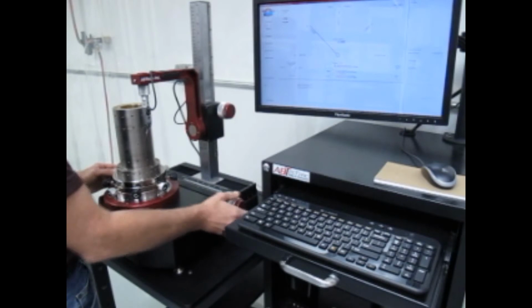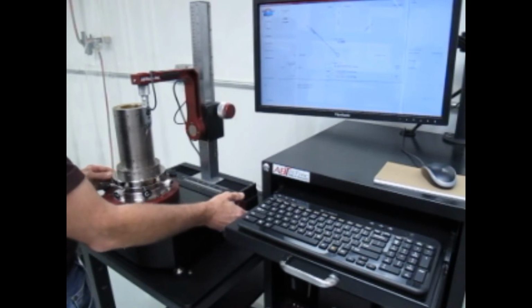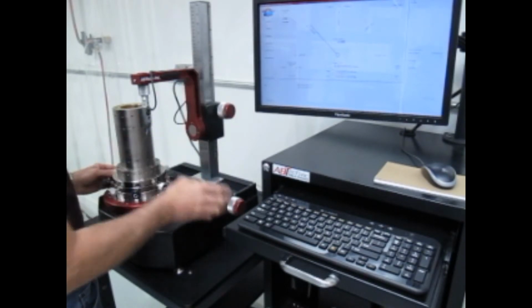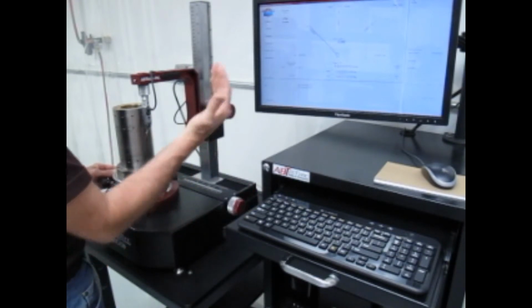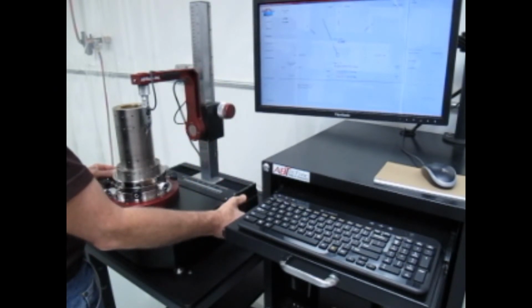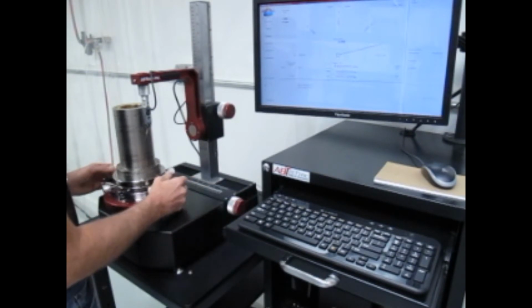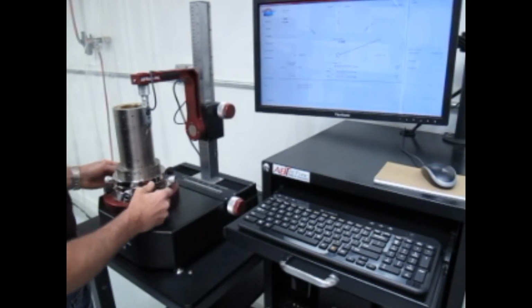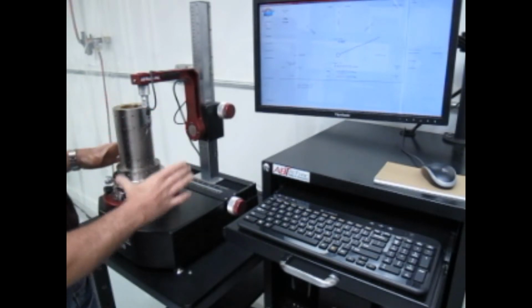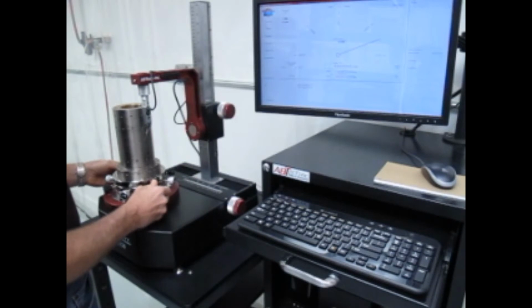So what I'm going to do is find the max point of where the probe is in contact, where it's displacing the most. Then I'm going to translate the whole gauge stand closer so that I'm maximizing that probe without going red on the other end, because it will pin and become red and it's not reading. So I'm there. I'm going to find my nearest black set of knobs, the centering knobs, and I'm going to move the work table, not the part, but the work table with the part on it, away from the probe until it stays black.